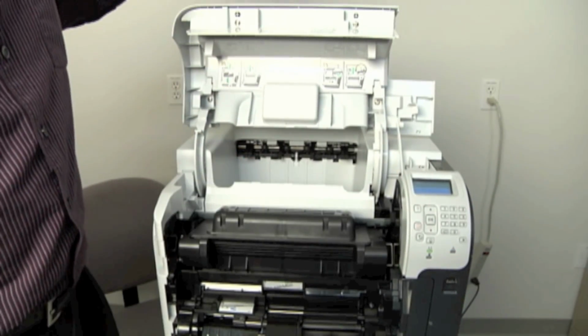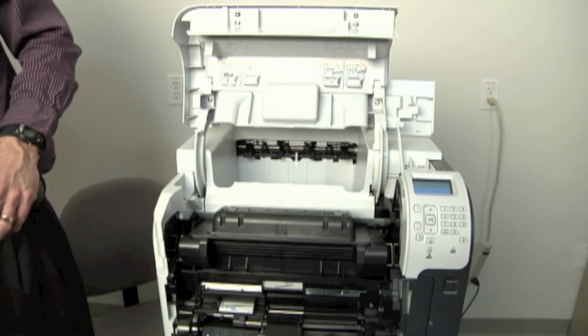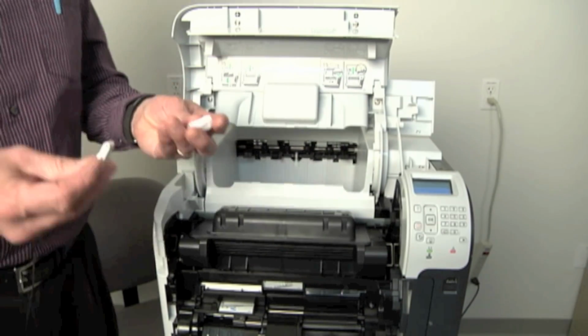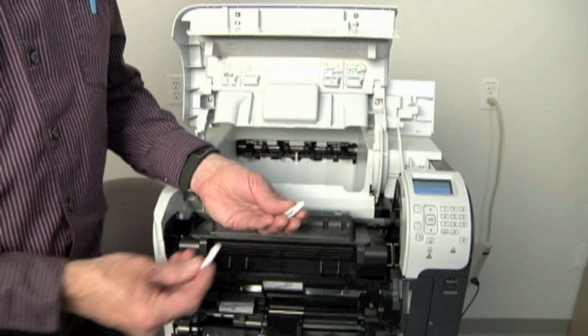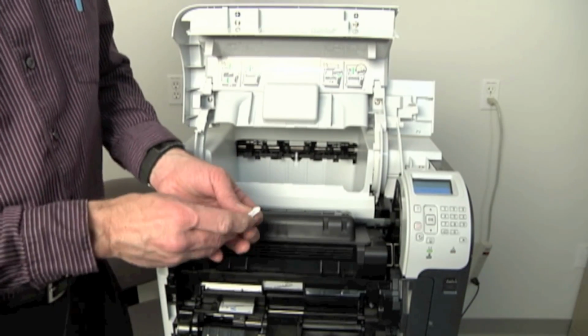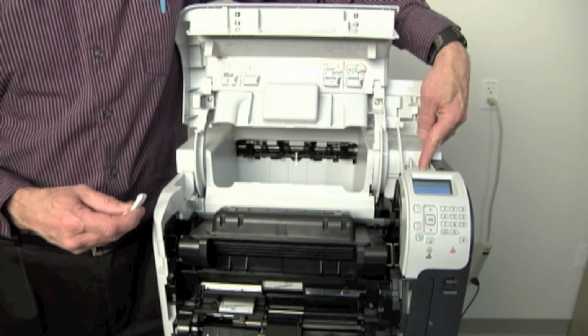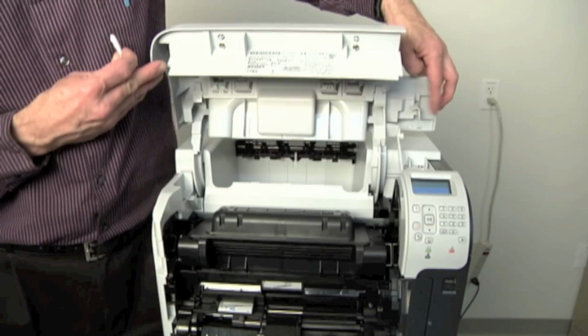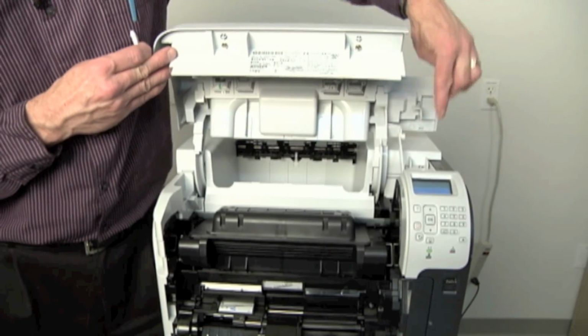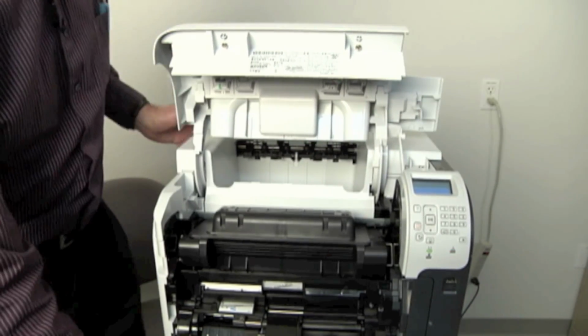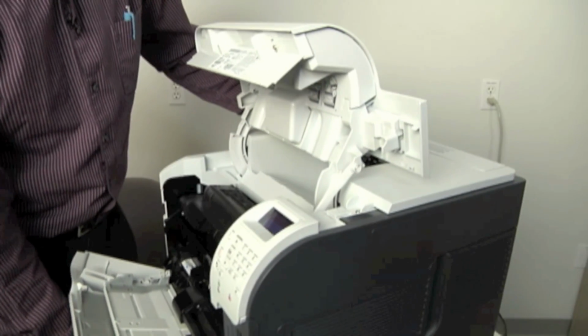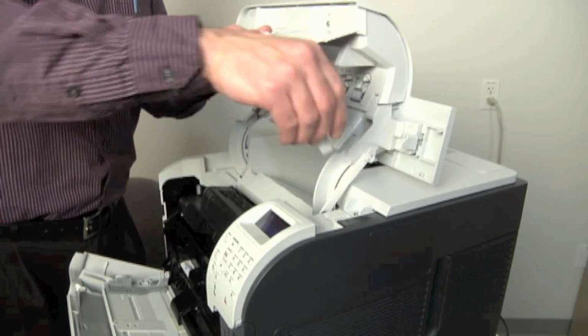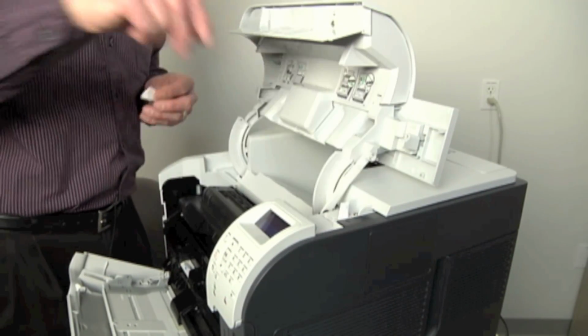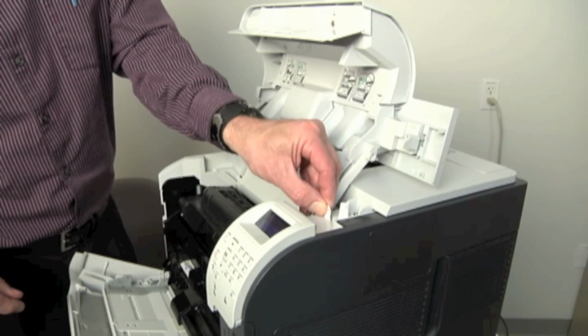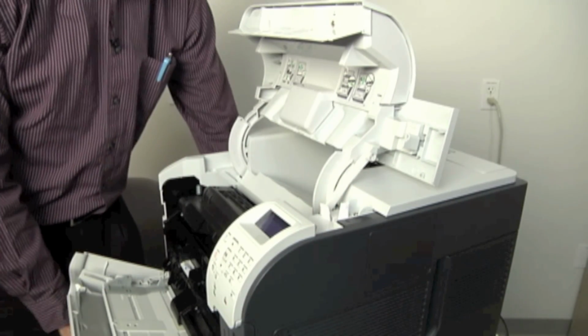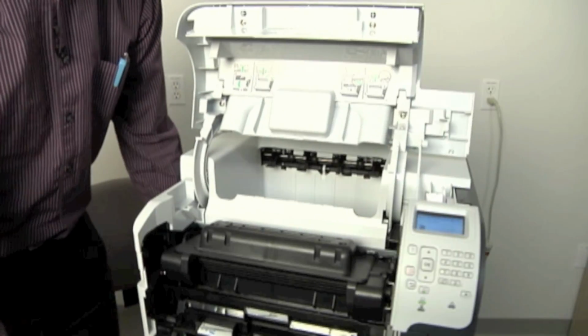Now it thinks the door is still open, but I need to create some cheater pieces of paper here for my interlock. I've got a couple pieces of paper, wad it up, and it's going to go into the interlock behind the display. You'll notice this little L piece on the cover - that's going to insert into this little pocket over here. If I turn the machine a bit, you can kind of see it. I'll put one piece of paper here so it thinks the door is closed, and the other one goes here - there are two switches in there. Aha, now it thinks the door is closed.